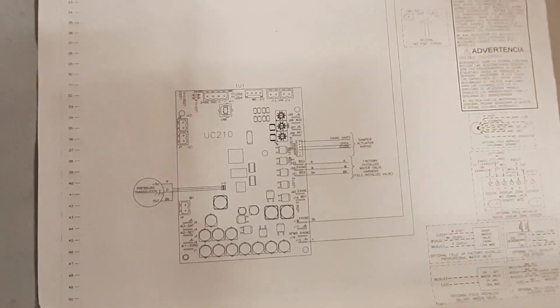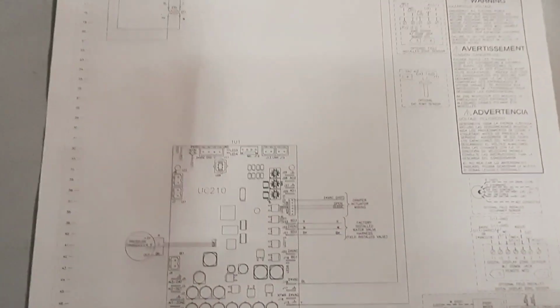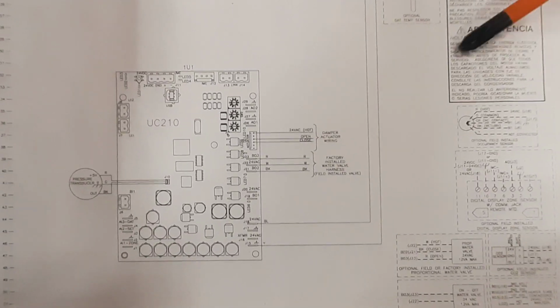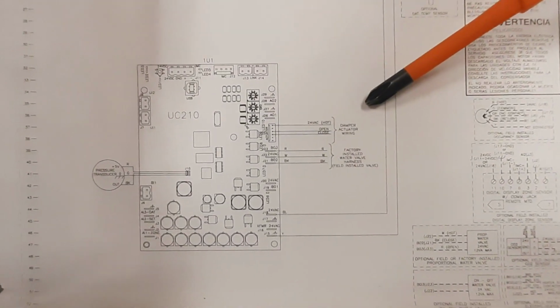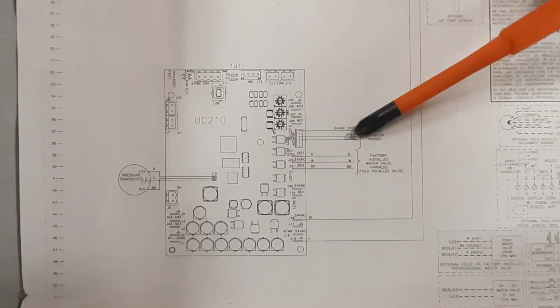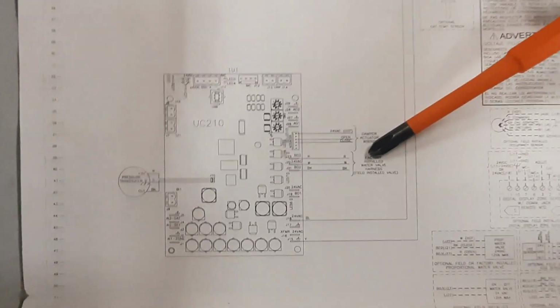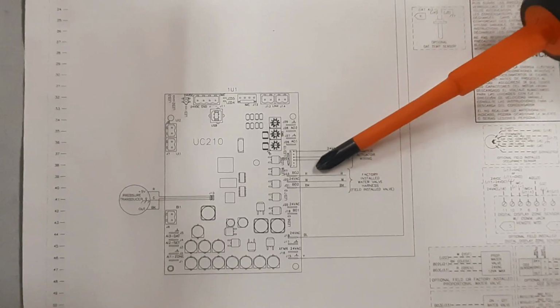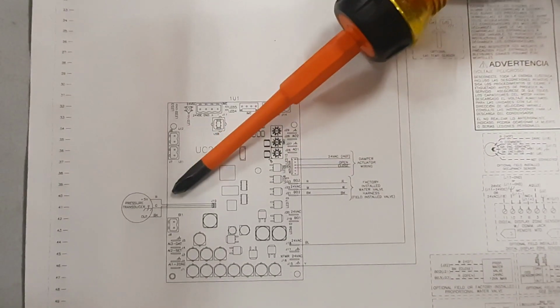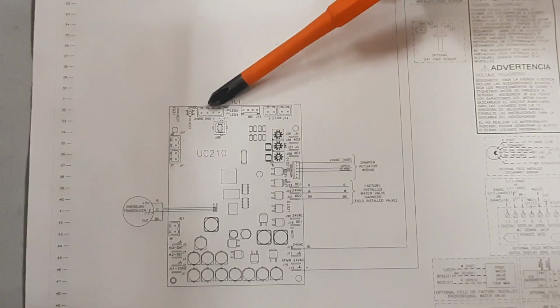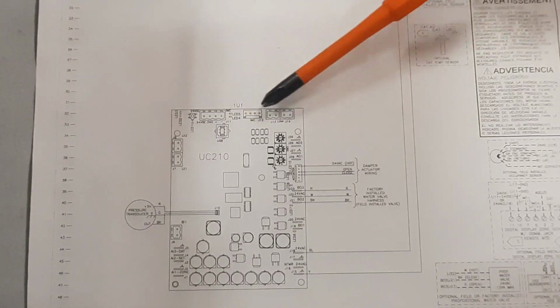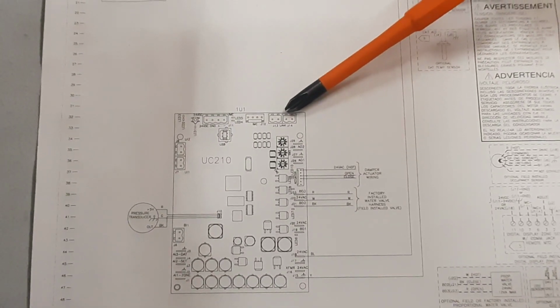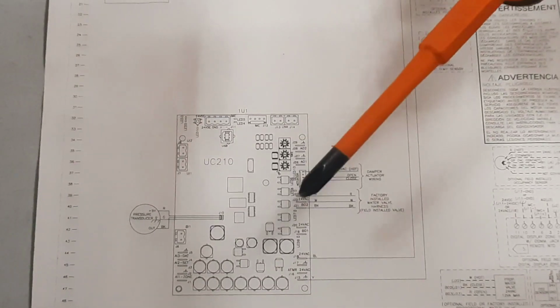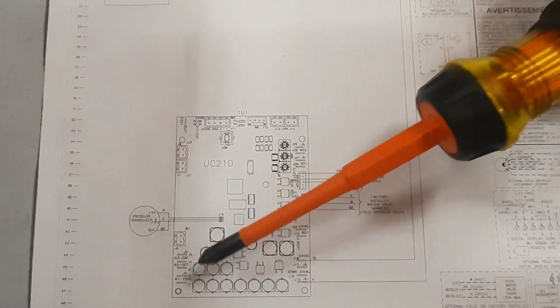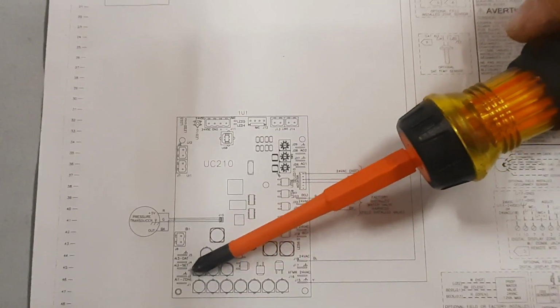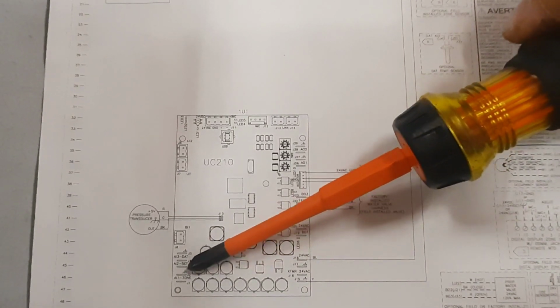So here's our diagram here. It's a UC210. You can see our damper actuator here. Field installed water valve. It's our pressure transducer. This is 24 volts in over here. The LON link is going to be my comm wire. It's usually purple shielded. And then we've got 1, 2, and 3 zone, ground, and set.